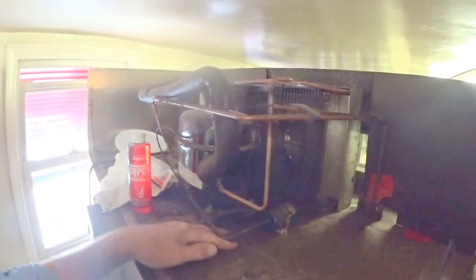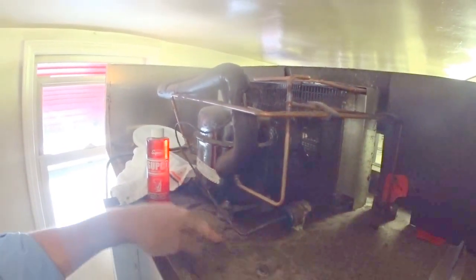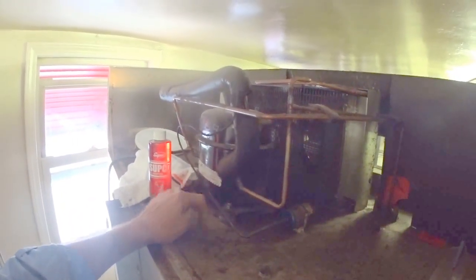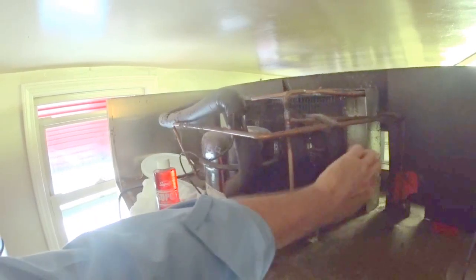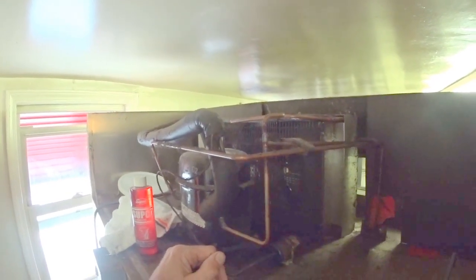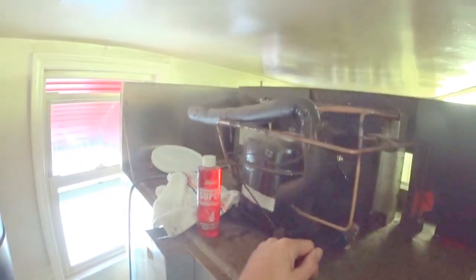This particular box, they mounted it right. This condensing unit doesn't have a base to it. To save money, this company mounted the compressor directly to the deck, and the same with the condenser. But I'm going to be taking this fan guard off because we don't have pigeons in here. That's what we're doing. It's a Tecumseh compressor.